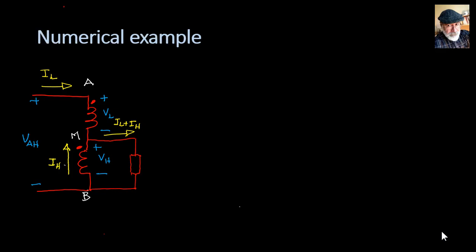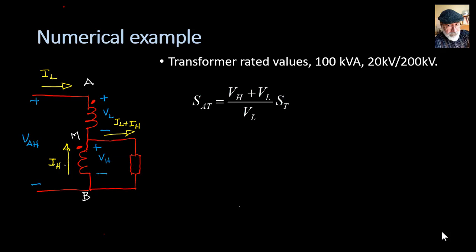We engineers like our numbers, so let's run a numerical example. Let's take a single phase transformer rated for 100 kVA, 20 kV on the lower side, 200 kV on the higher side. If we just set up an auto transformer with that single phase two winding transformer, we compute that even though we could feed only 100 kVA of load with a single phase transformer, with the auto transformer built with the same single phase transformer, we can feed 1.1 mega volt amperes, that is 1100 kVA, 11 times more power. Isn't that amazing?